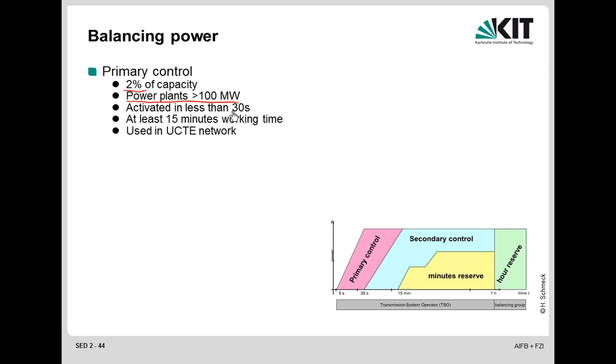So again, primary control: the facts that I list here are the traditional facts which were valid up to something like 5 years ago. Things have changed dramatically since then because people noticed we need more possibilities to provide primary control power, even from smaller power plants. It used to be that only large power plants with more than 100 megawatt in power generation could provide that. And they were supposed to provide 2% of their capacity as primary control. That means they were supposed to be able to increase or decrease their power generation by 2% within a few seconds, at least the complete 2% of the capacity, so at least 2 megawatt, within 30 seconds, with at least 15 minutes working time.